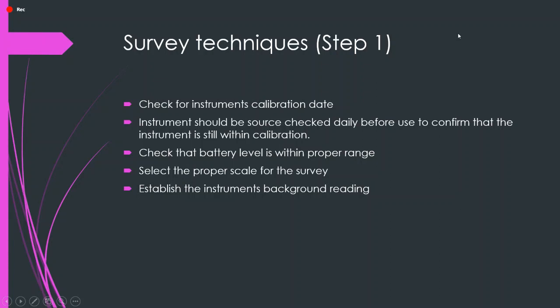So the first thing you should be doing is checking the instruments to make sure that they are within the calibration period. ISU is now doing an annual period, so our period between calibrations is a full year instead of half a year. Make sure it's within calibration. There should be a sticker on the side with a calibration date and who calibrated it, whether it was Qualitech or somebody in the EHS office. Depending on the instrument, sometimes we have to send them out. So check the calibration date.